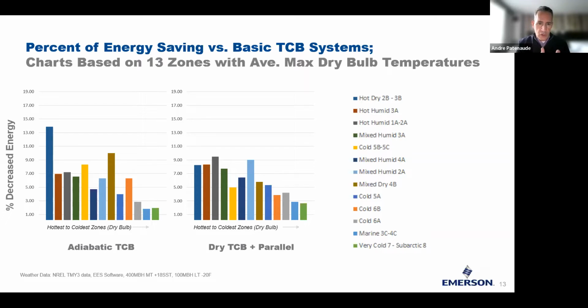But in that same zone, you go to the middle chart, that dark blue line to the left, with parallel compression by itself gives me around 8%. So on the chart on the left, 4 of the bars are taller with adiabatic. Those are those 4 climate zones where you had less than 30% average relative humidity. Adiabatic outperforms parallel compression there, but in 9 out of 13, because there's already moisture in that air, parallel compression from an annual perspective outperforms adiabatic by itself.